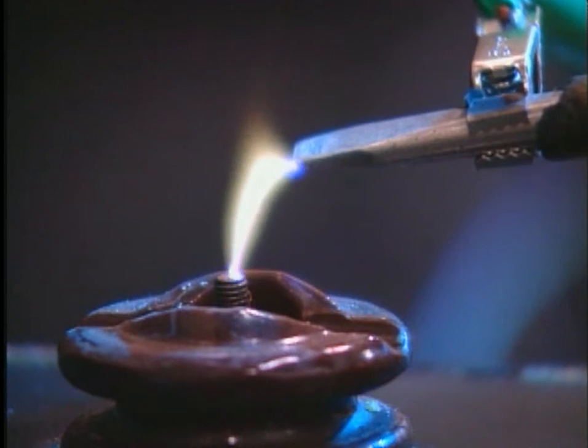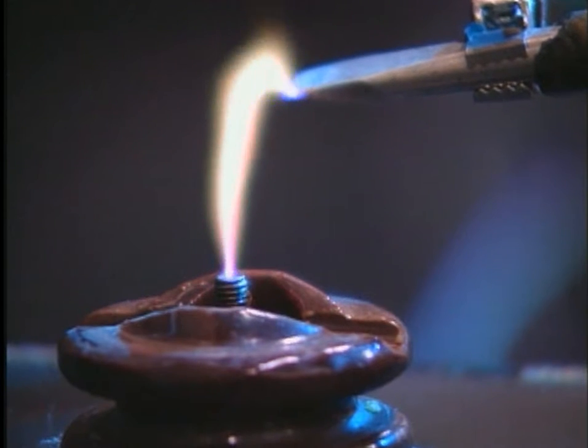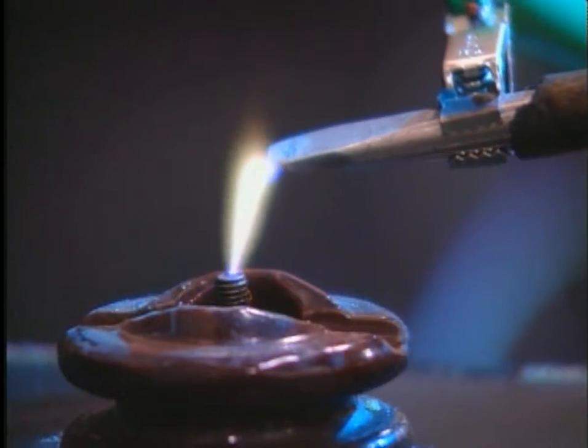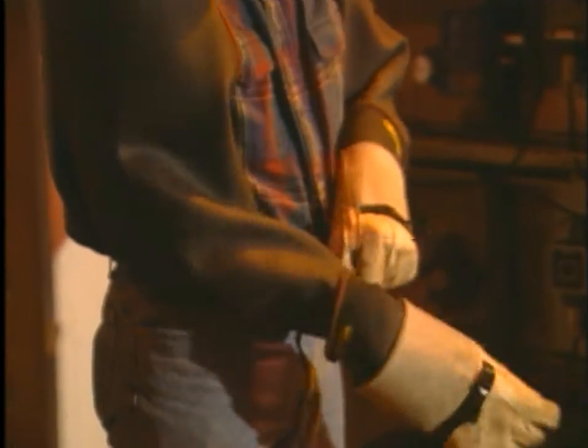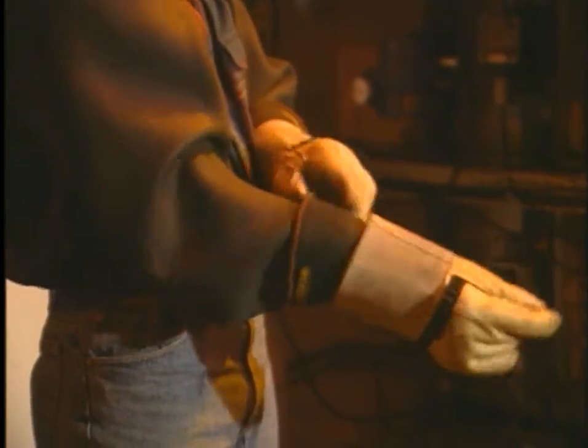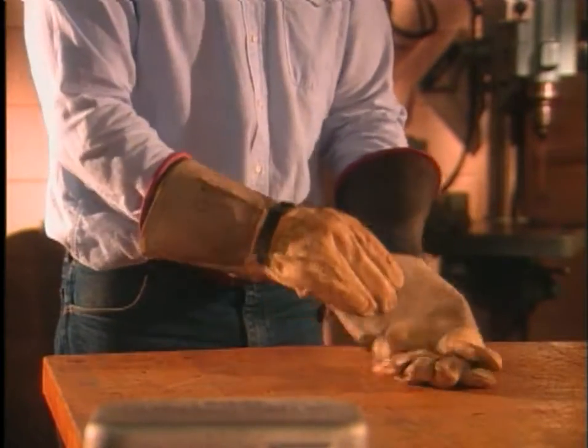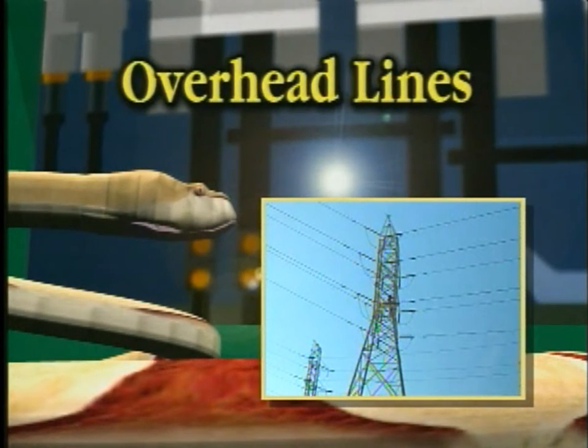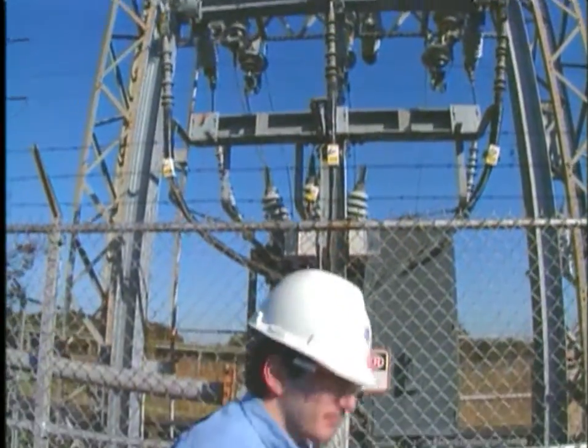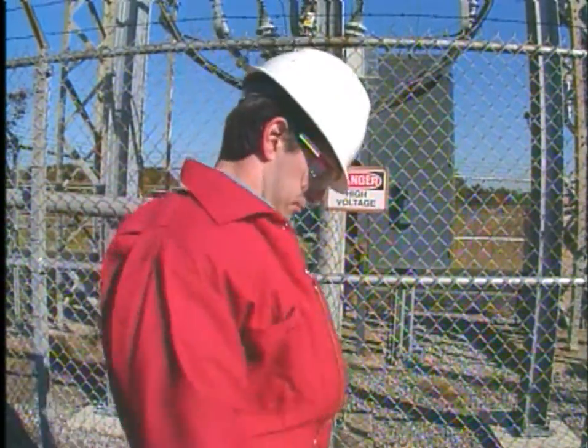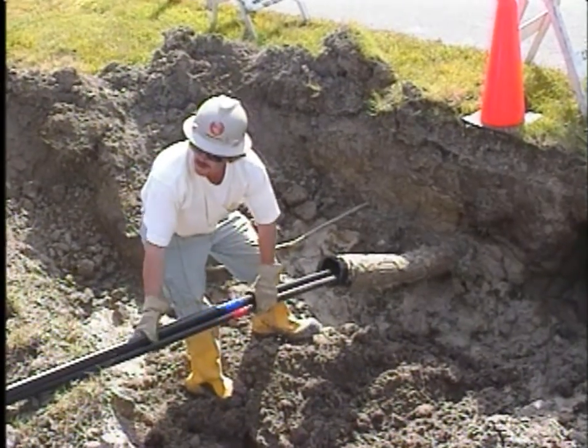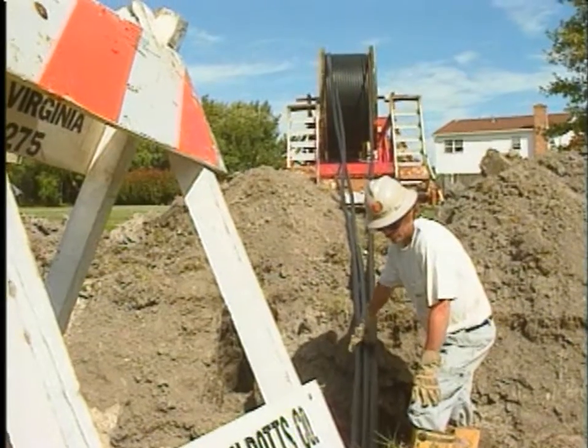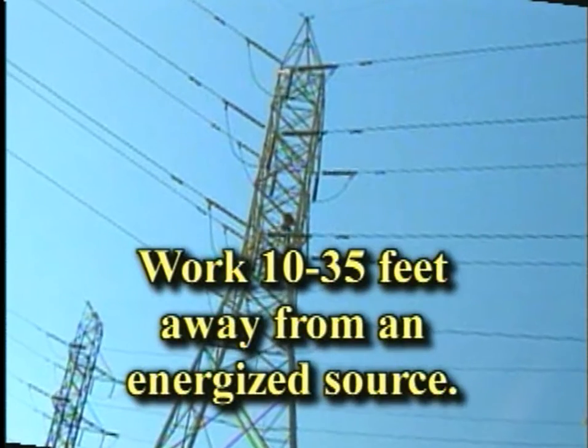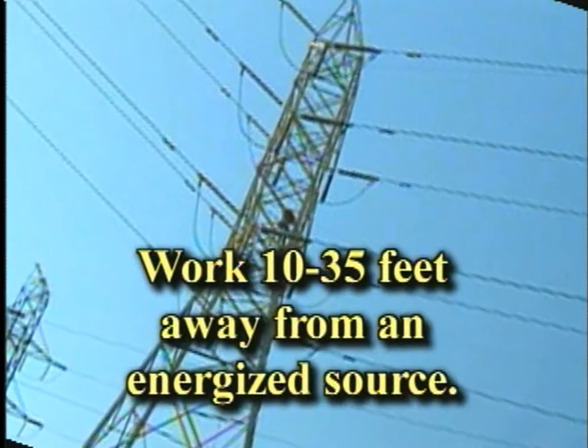If a conductive object, such as a screwdriver, wrench, or fish tape, contacts a live part and then ground, you are in fact welding until an overcurrent device trips the circuit. Do not use your own safety equipment unless it is approved by your employer. As with all your equipment, inspect and test your PPE before use and protect it from damage. One way to protect rubber insulating material is to use an outer leather covering. Although all energized circuits are electrical hazards, none have caused more deaths than overhead power lines. Just like a contained snake is a safe snake, a safe overhead power line is one that has been de-energized and grounded. The rule of thumb is to work from 10 feet to 35 feet away from an energized source. Even experienced qualified people cannot identify line voltage by eye.